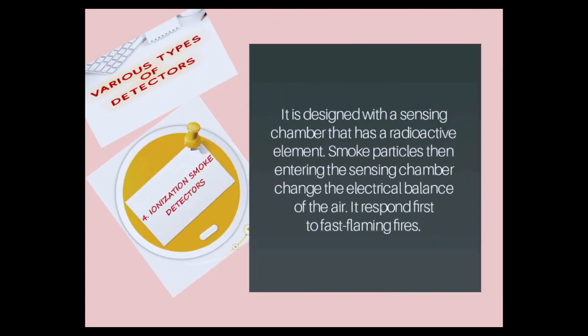The fourth type is the ionization smoke detectors. It is designed with a sensing chamber that has a radioactive element. Smoke particles entering the sensing chamber change the electrical balance of the air. It responds first to fast flaming fires.